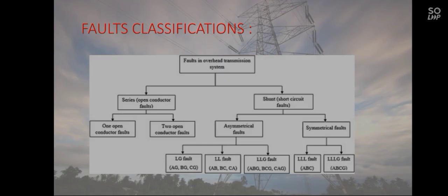Fault classifications. Faults in an overhead transmission line system are classified into series or shunt. Series faults are called open conductor faults and shunt faults are called short circuit faults. The series faults are classified into one open conductor fault and two open conductor faults. And short circuit faults are classified into two types. They are asymmetric faults and symmetrical faults.